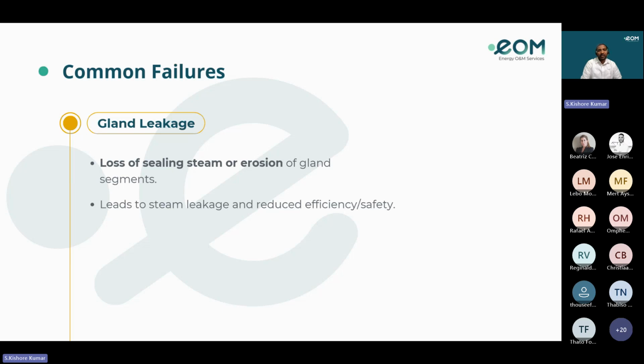So always maintain the recommended pressure and temperature in both the lube oil and the gland sealing, and maintain proper clearances while doing the outages of the steam turbine. Also, during every shift, please check the gland drains for any traces of oil. That is also one of the important points we all have to check, as it shows the early signs of leakage. Sometimes it is not seen. And yes, gland leakage can also cause major problems, and it causes fires in a lot of turbines. So always be attentive, and whenever there is a chance, please rectify the gland seals and always maintain proper clearance for the glands, both oil and steam glands.